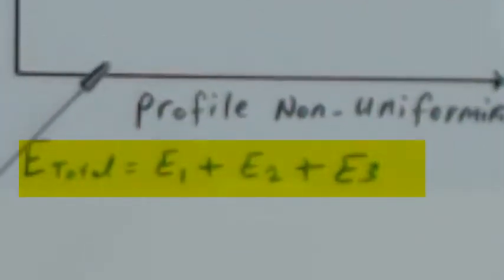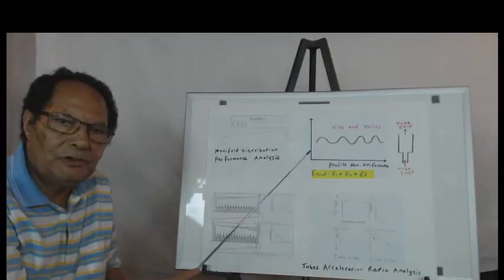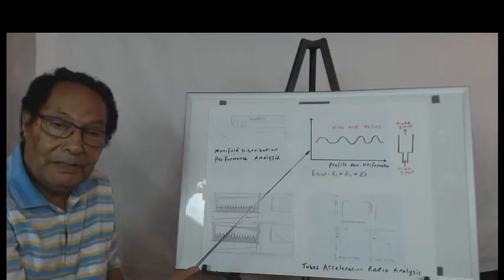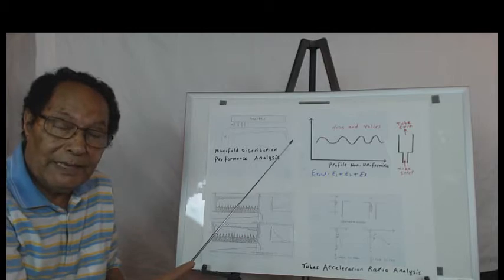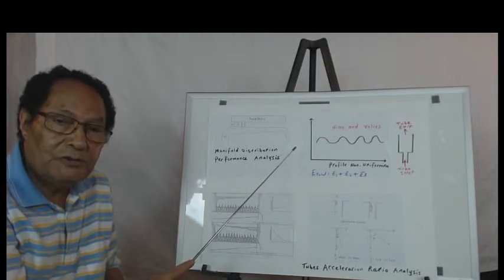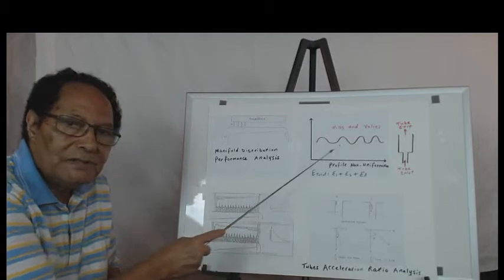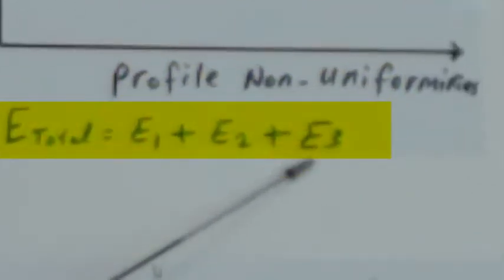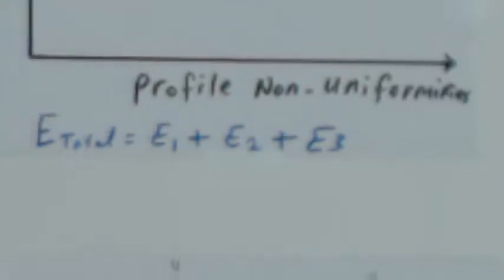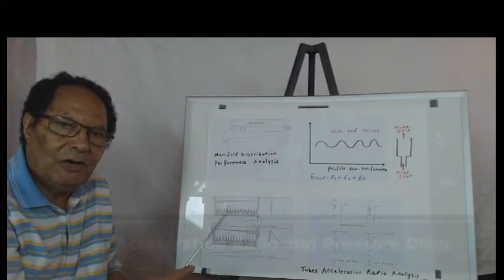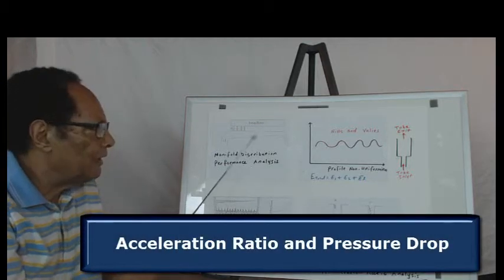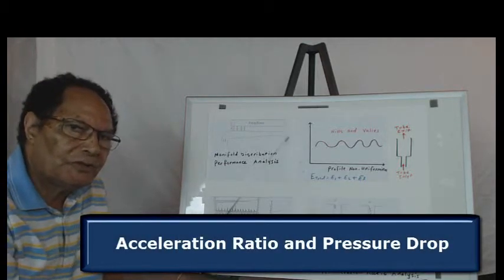E2 is the pressure drop through these tubes. If the tubes have fiber buildup inside or at the inlet, you end up with different pressure drops, different non-uniformities. E3 is very important. I don't want to go into too much calculation detail, but it's based on the acceleration ratio and pressure drop through the tubes.